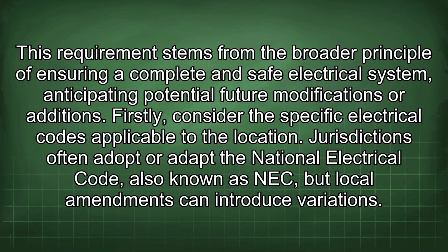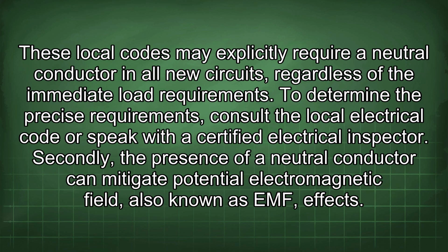modifications or additions. Firstly, consider the specific electrical codes applicable to the location. Jurisdictions often adopt or adapt the National Electrical Code, also known as NEC, but local amendments can introduce variations. These local codes may explicitly require a neutral conductor in all new circuits, regardless of the immediate load requirements. To determine the precise requirements, consult the local electrical code or speak with a certified electrical inspector.